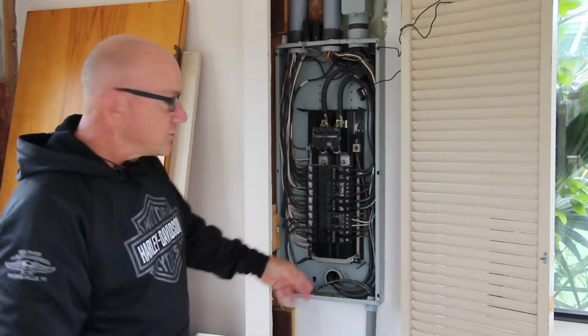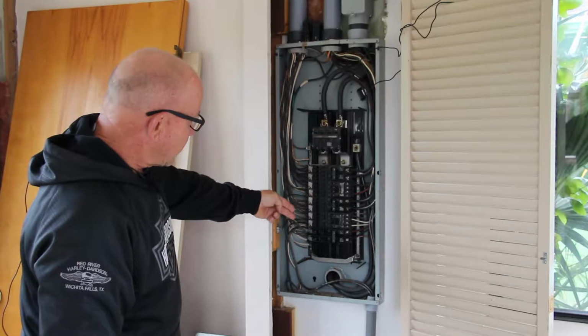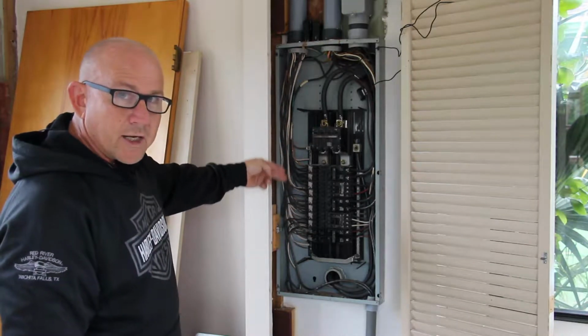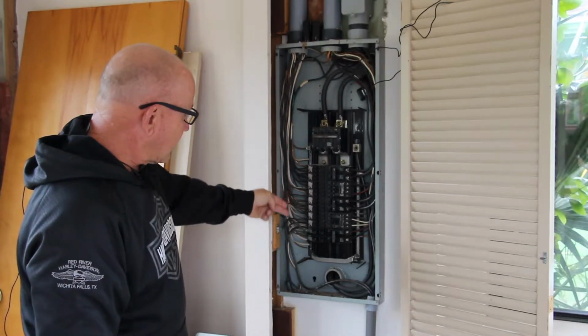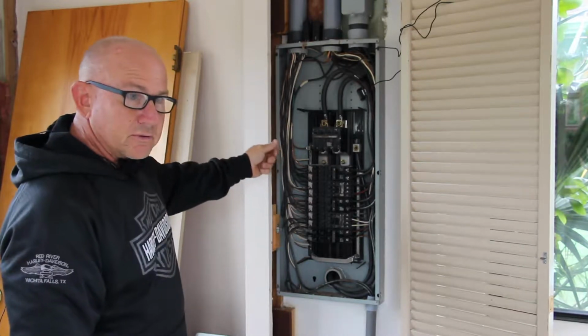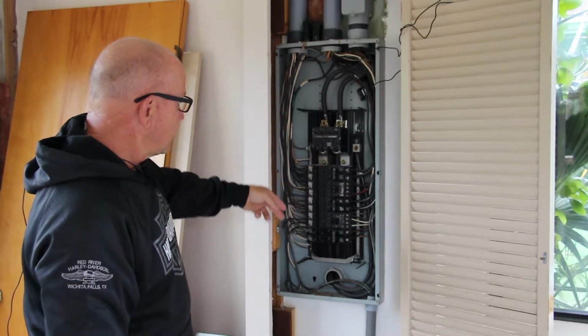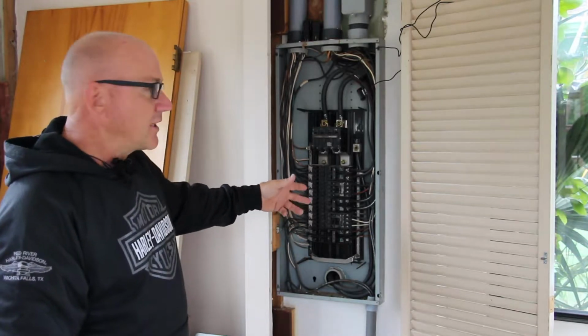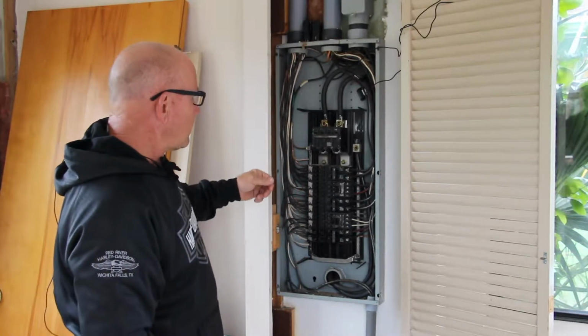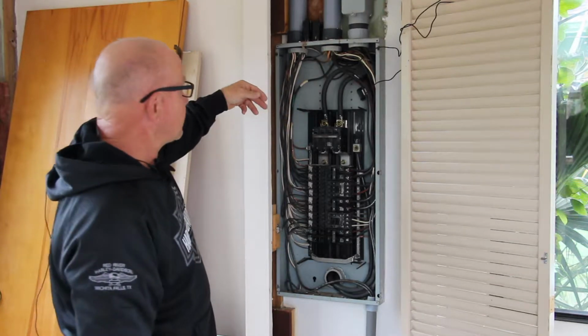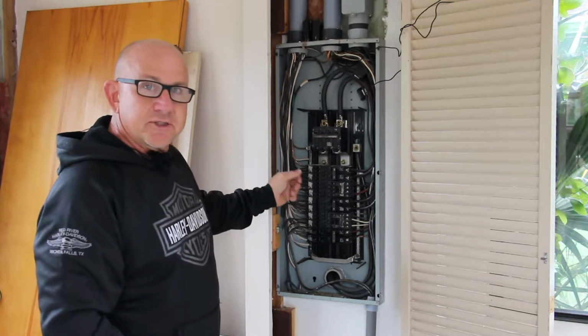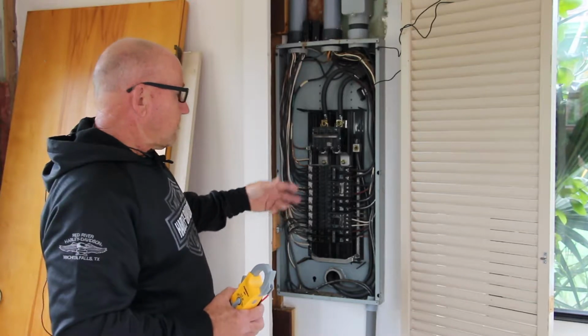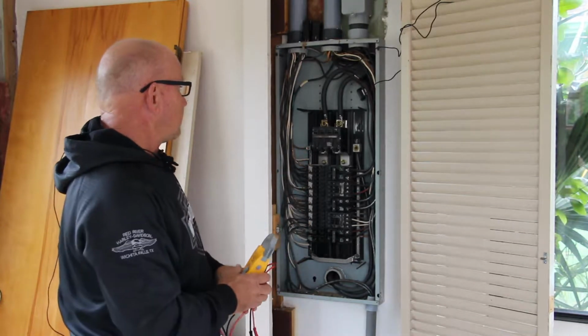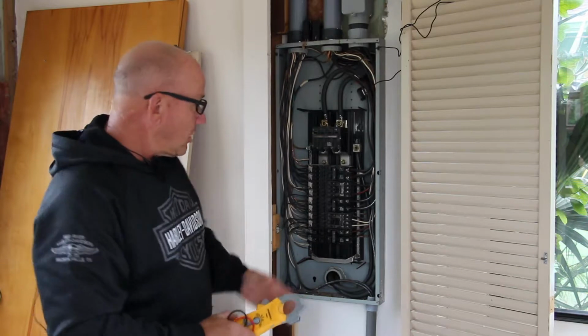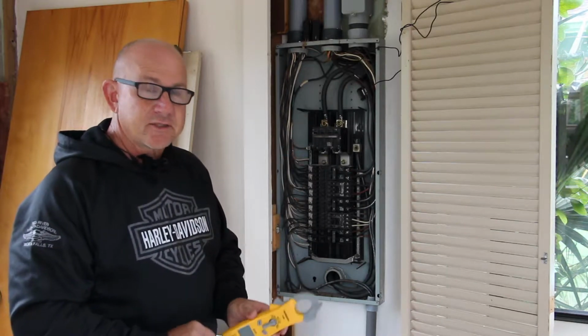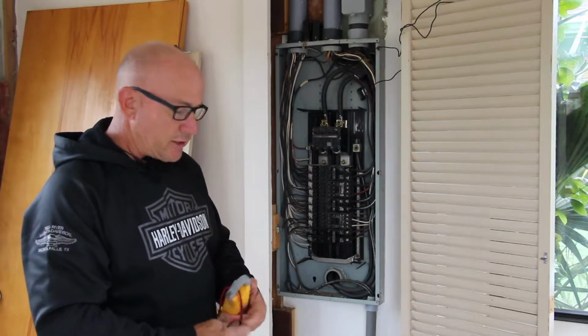The next thing we want to do is look at all the circuit breakers. Make sure there's only one wire on each breaker. Make sure that they're black wires. Those are the hot conductors. If there are any white wires on the breakers, they need to be identified as black. We want to look for any cut conductors. We want to make sure that the breakers are compatible with the electrical panel. We're not going to turn the electricity on at the main breaker in this particular case because of some other conditions here at the property.